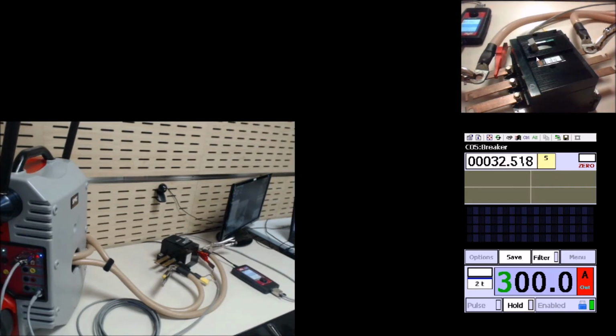You will see the tripping here, and you will hear the noise of tripping as well. So we have a trip here at 66 seconds. It's very typical that this trip time goes down when I repeat the test, because in the very first test, the breaker is cold, which is not the normal operating situation. Normally, a circuit breaker in operation has a temperature. So the thermal element is, of course, sensitive to the initial value of temperature in the internal conductors.